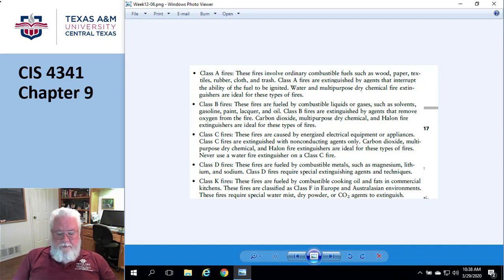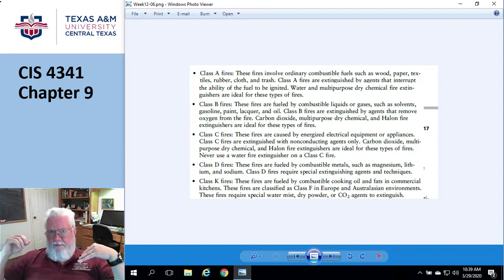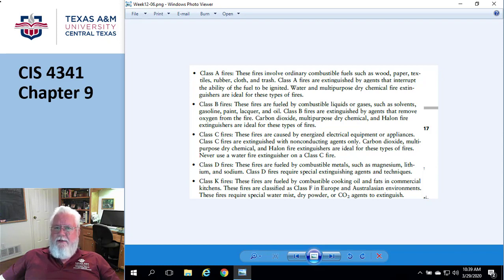Okay, gaseous emission systems. So halon gas, again, that used to be really big, now it's not. What they want is something that's called a clean agent, something that if they dump it into the room, you don't have to go back and clean up afterwards, right? So CO2 is a fantastic one. If they dump CO2 into the room to suppress the fire, I don't have to go back with a vacuum cleaner or a broom and clean up everywhere, because it's just a gas that went away, right? So no residue is the key to that. And CO2 is fantastic, but for God's sake, you better not be in the room.